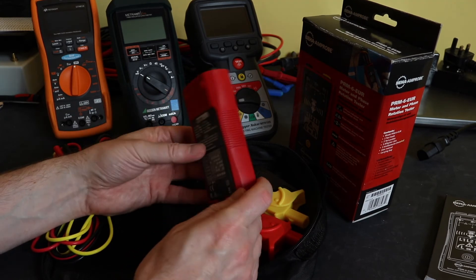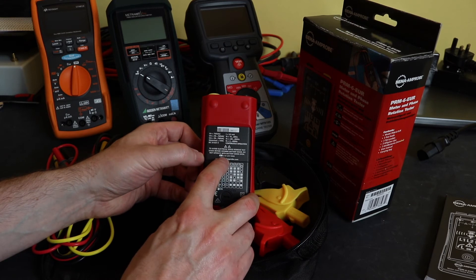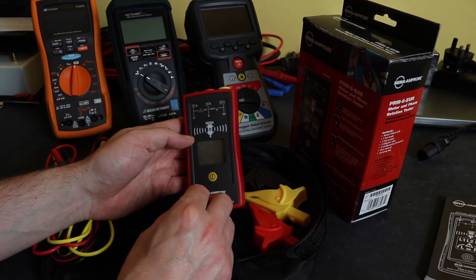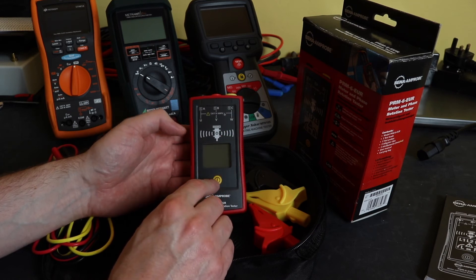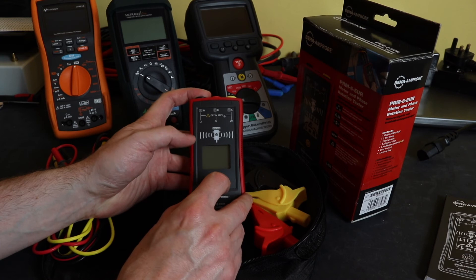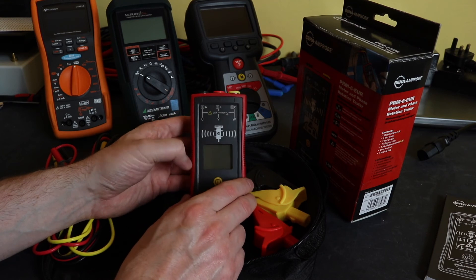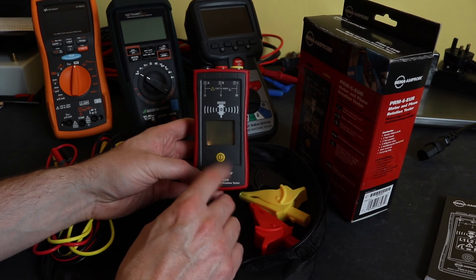This is battery powered for the motor tests — two AAA batteries — and it gives you a display on the back for the configuration of the lights, although it's actually an LCD display. It will do phase rotation of the supply when you plug it into the jacks. When you put this onto a disconnected, de-energized motor, you can press the button, spin the motor, and it will give you a left or right rotation. With the motor energized and running, you can hold this against it — it has a magnetic pickup that will also give you rotation direction.